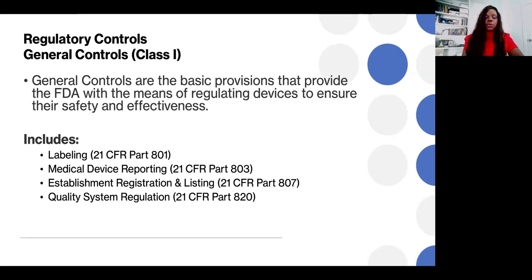And then there's the quality system regulation. I think whether it's an exempt product or a class 2 or class 3 product, you need to set up a quality system and make a decision based on the risk, which sections are applicable for your device.